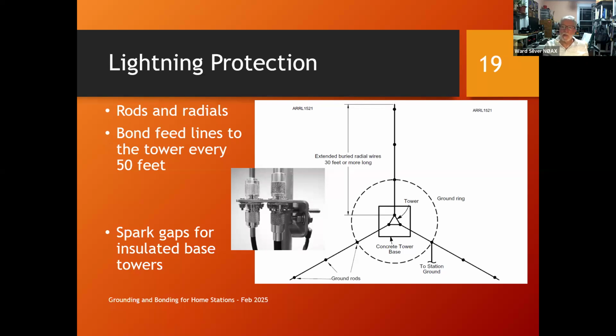But if you don't, remember that number 12 wire that had the lightning current flow through it, and it had 761 volts from end to end. A typical tower can develop 100,000 volts between the top and the bottom when hit by lightning. It's not uncommon. And if you don't have your cables bonded to the tower, there will be 100,000 volts between the cable shield and the tower. And that's when you blow up your cables, you get pinholes and splits and all sorts of other nasty things. So unless you like troubleshooting and replacing cables, make sure you bond the cables to the tower every 50 feet. If you have an insulated base tower, put a spark gap down there.